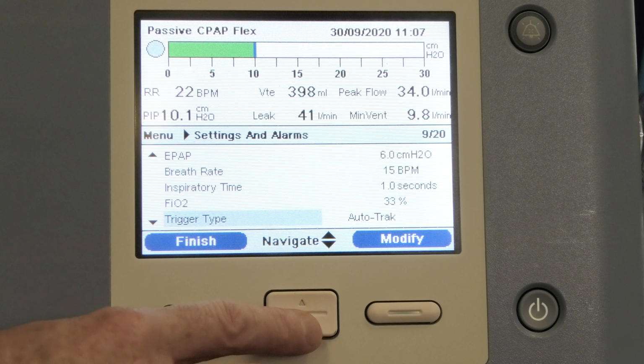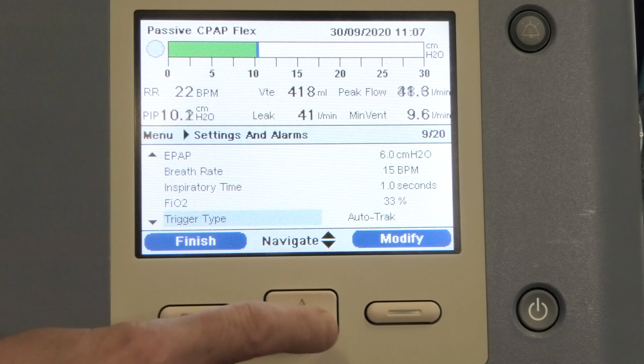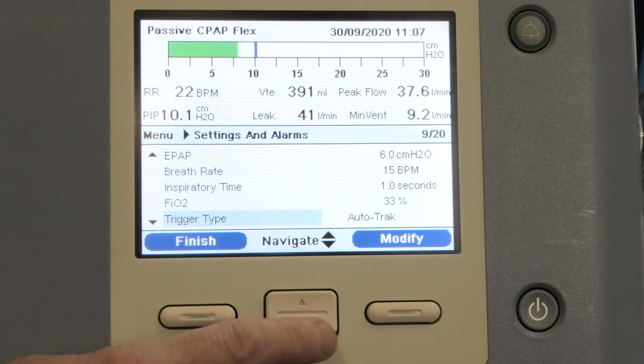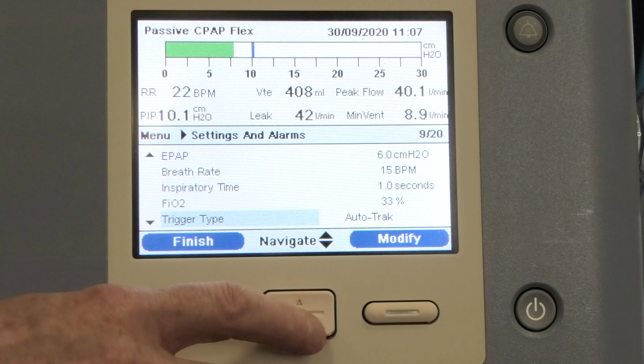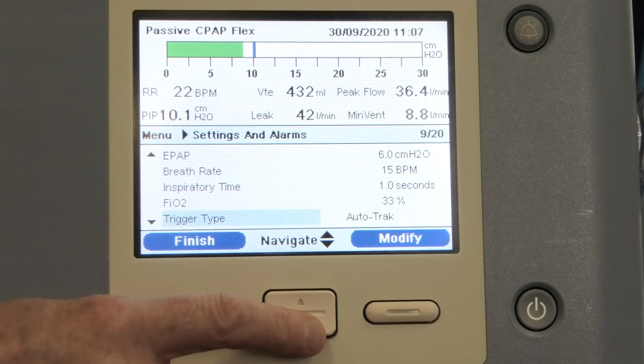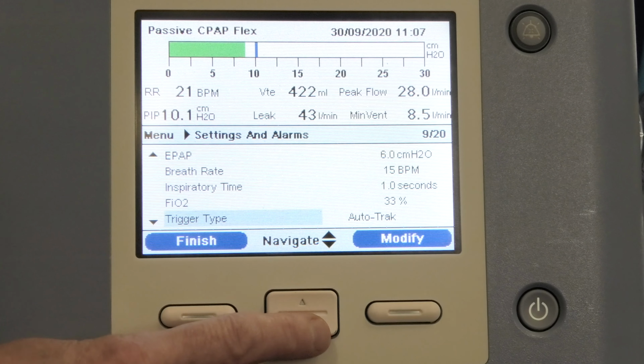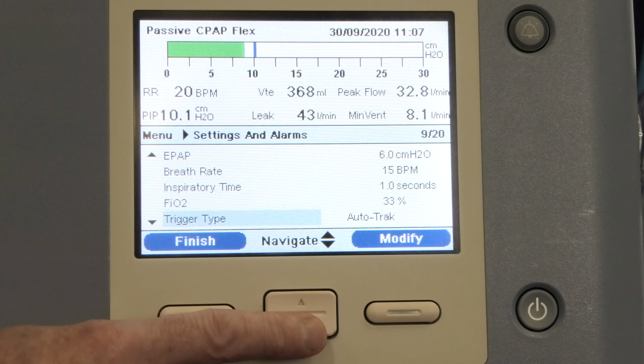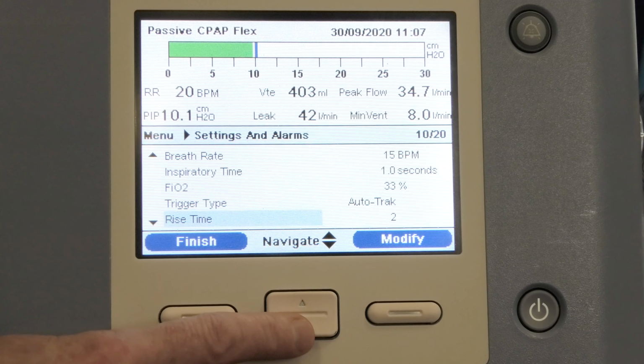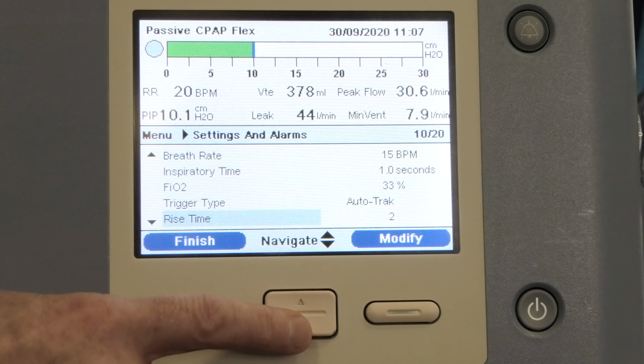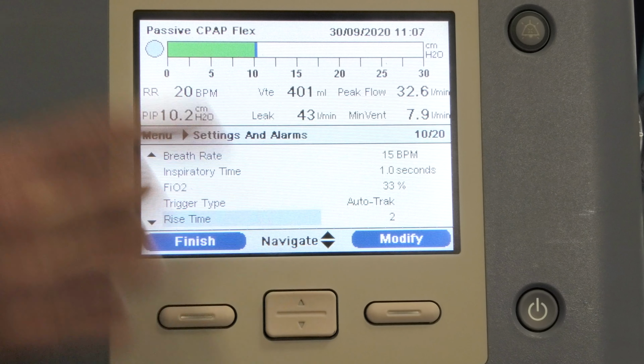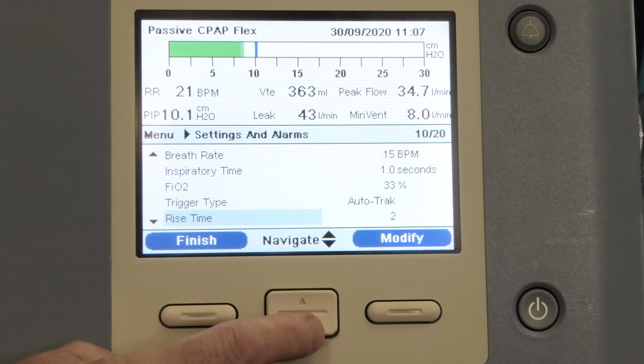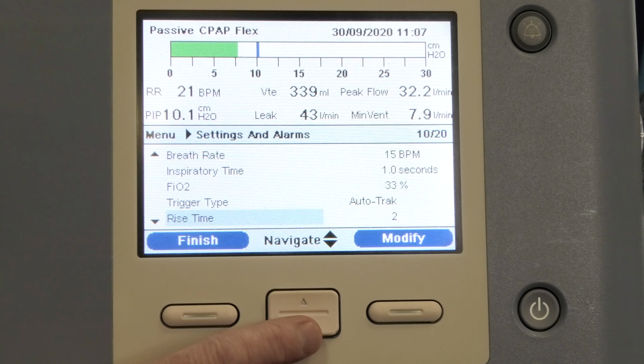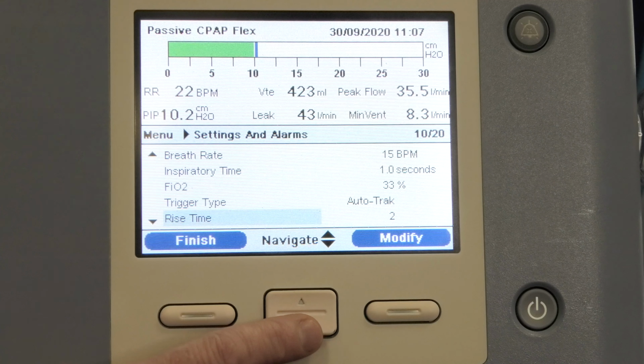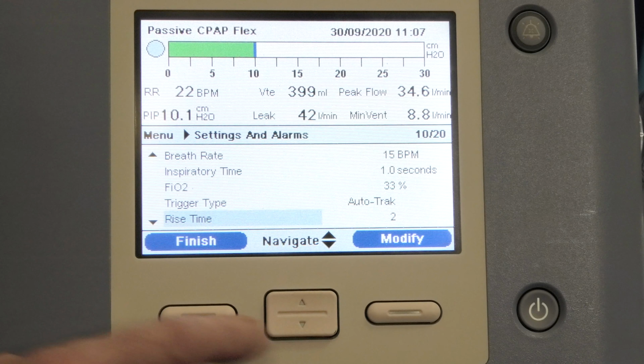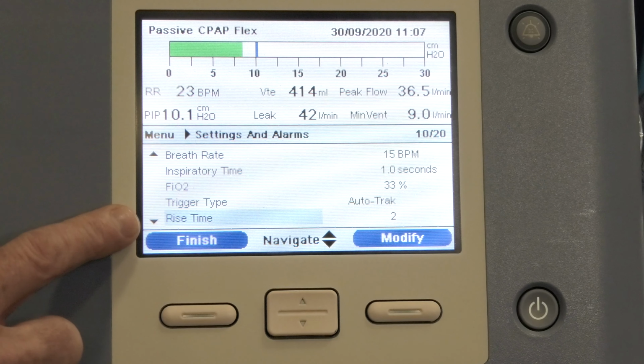We have our trigger type, which always needs to be Auto-Trak. That's an adult-based tracking system for the ventilator to pick up when you're cycling from inhalation into exhalation and exhalation into inhalation, and it makes it seamless and very comfortable for the patient. There is a flow trigger and a sensitive trigger, but they're for paediatric patients, so for adults they need to be in Auto-Trak. Our rise time is our rise to pressure. 1 to 6 is what Respironics use. 1 is the fastest rise time and 6 is the slowest rise time. Essentially you want your patient to be hitting their pressure as early as possible when they're extremely tachypneic or unwell. So we would set our rise time between 1 and 2 for anyone with a respiratory rate of more than 30.